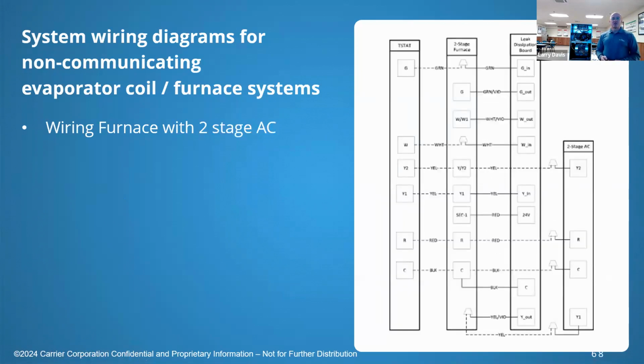Okay, and again for a two-stage, if you have any questions, we've looked at these. It's pretty straightforward. The outputs from the thermostat have to go through the dissipation board before they go to the furnace. Now, one thing you'll notice on the Y2, on a two-stage outdoor unit, there's not a Y2 terminal on the dissipation board, okay? The reason is that with Y2 all we're doing is energizing a solenoid. So if we go into the dissipation mode, we're going to kill our Y1, our compressor is going to stop anyway. So there's no point in breaking that Y2 through the dissipation board. That'll just run straight through from the thermostat to the terminal on the furnace to bring our fan into high stage during Y2, and then right out to the outdoor unit.